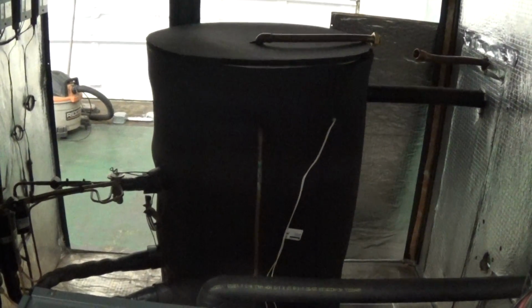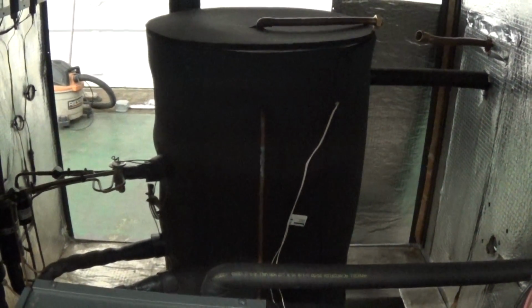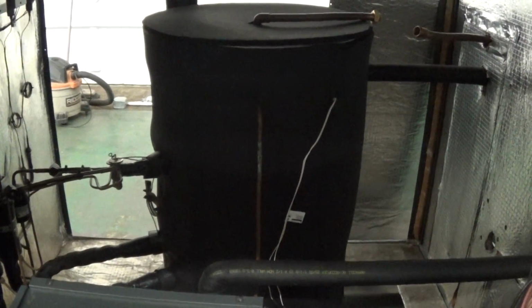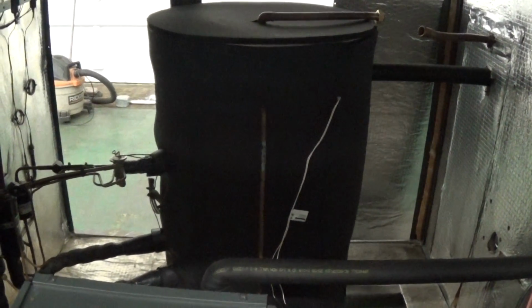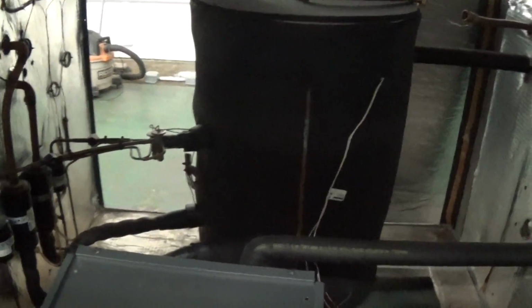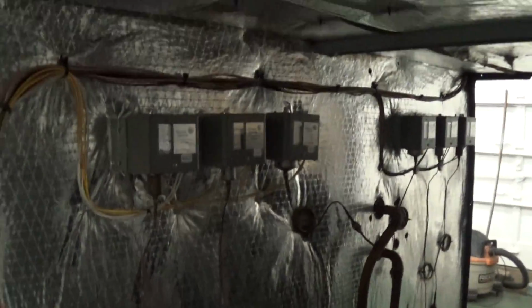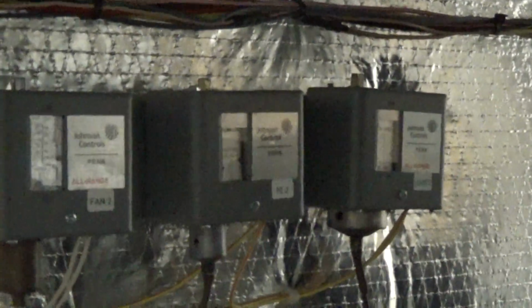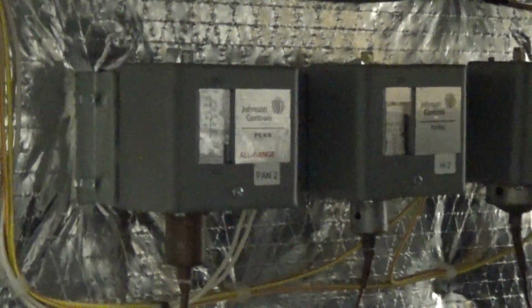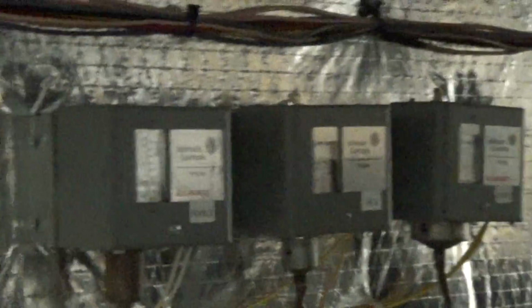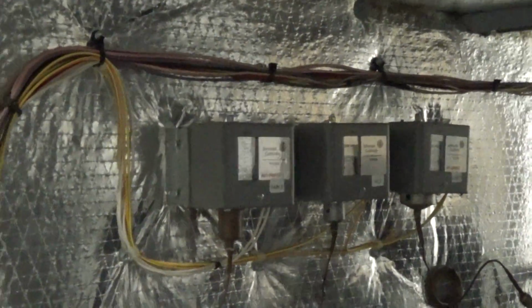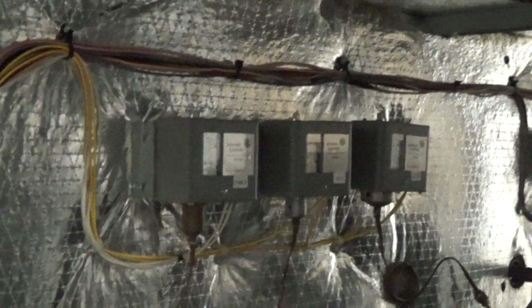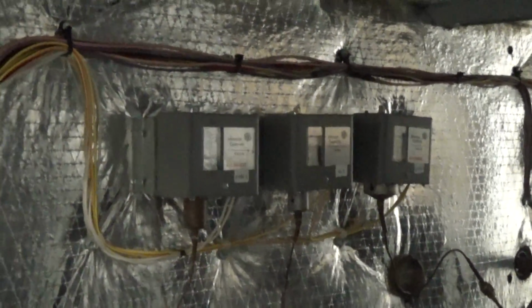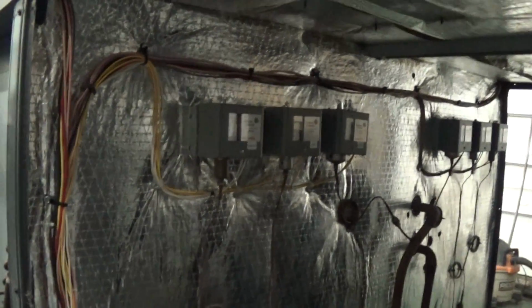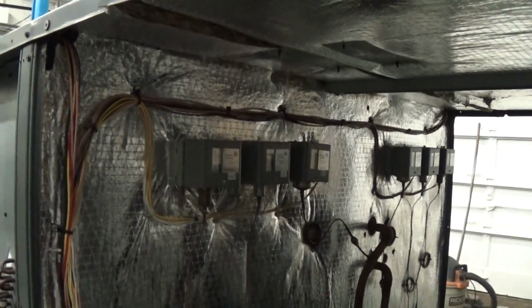So if one compressor goes down, you still have 50% of your cooling capacity until that compressor gets fixed. So again, you've got 2 heat exchangers, 2 circuits. Each one of your circuits has a high pressure switch, a low pressure switch, and a pressure switch for the fan. This has low ambient, and that's what the fan pressure switch is for. So this can run down into the minus 20, minus 30 Fahrenheit range outdoors. This is an outdoor rated chiller.